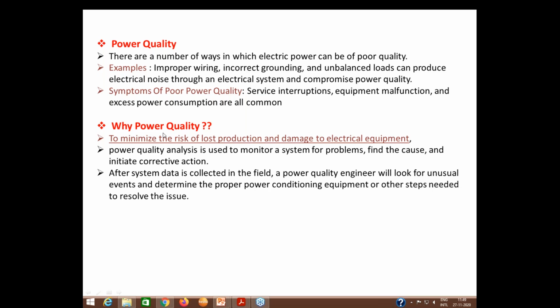Suppose you have a special purpose machine in your industry that costs crores of rupees, and you connect it to the electricity board or power supplier. If power quality is not consistent, with continuous over voltage and under voltage phenomena, that may damage your machine. So power quality study, analysis, and scanning need to be done periodically, if not daily, at least periodically, to minimize risk of production loss and equipment damage. Power quality analysis is used to monitor system problems, find causes, and take corrective actions.